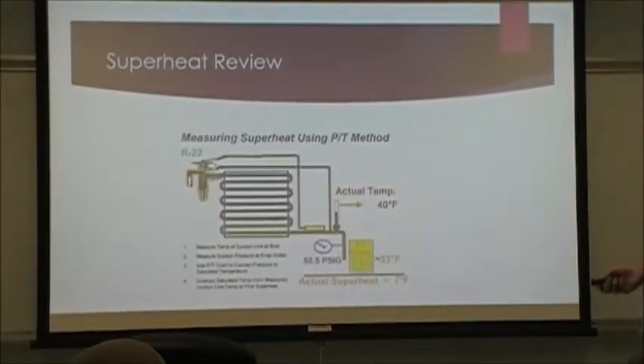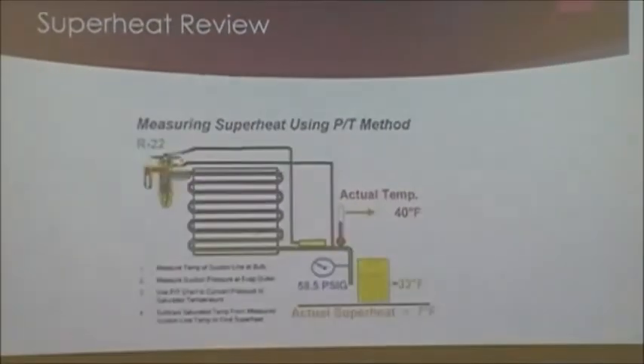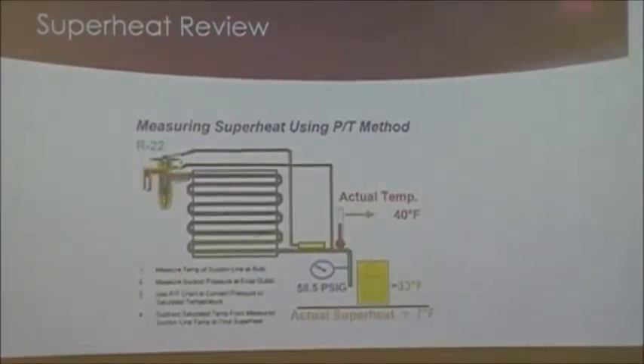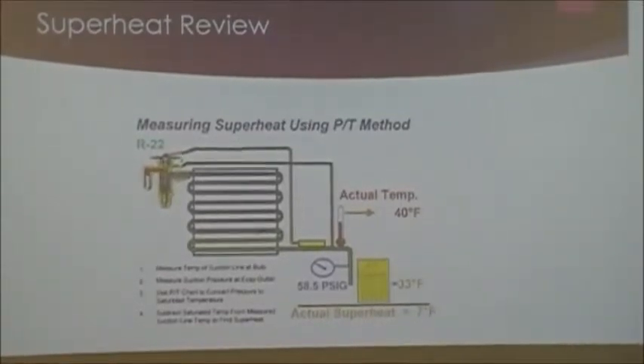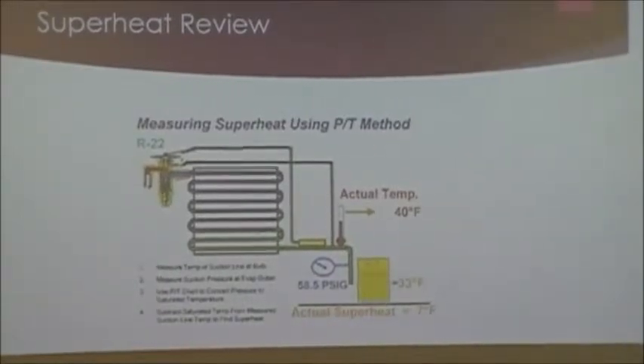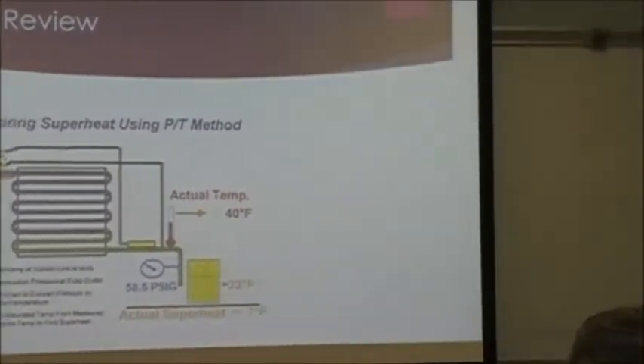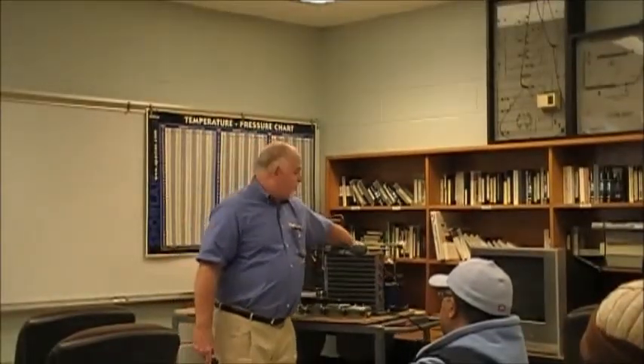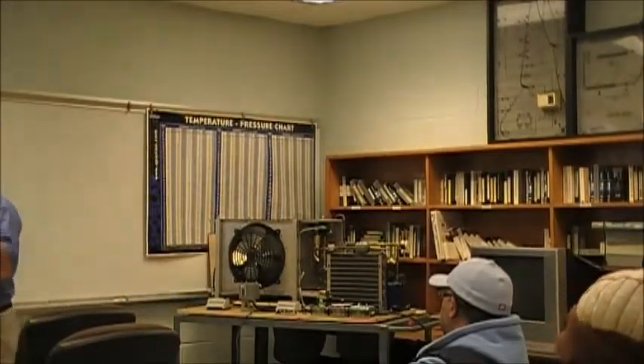Okay, superheat. The reason we need superheat is because we have to make sure that there's no refrigerant coming back to that compressor. As a matter of fact, when you're playing with this thing over the course of the next few weeks, I want you to literally cut the fan off and let it flood back, and you'll see, even though it's got this big accumulator on it right here, for the size of this thing, that refrigerant will still flood back to this compressor. So there's no 100% way of saying for sure that you're not getting refrigerant back, so it's imperative that we control superheat. Number one, to protect the compressor.